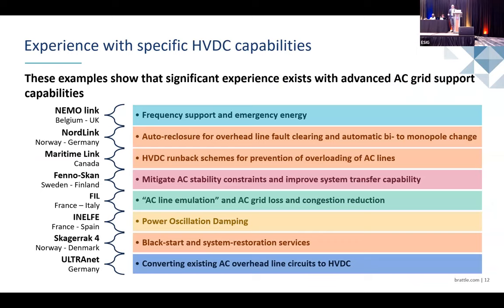As for the experience with specific capabilities, there are many examples here, just a few of them. They're being used for frequency support and emergency energy. The auto-reclosure for overhead line fault clearing has been tested. The interesting thing about the bipole configuration is that if you have a fault, it usually affects only one of the poles. So unlike an AC line where the entire line goes down, if one of the poles has a short circuit with the bipole HVDC configuration, you only lose half of the capacity. The other pole can keep operating. And importantly, even if you have a fault on the line, the converters can still pump reactive power into the systems. They don't need the line to be operating. Of course, you can't transfer any real power if that happens.